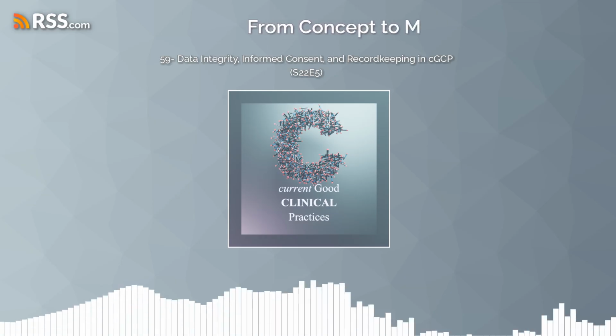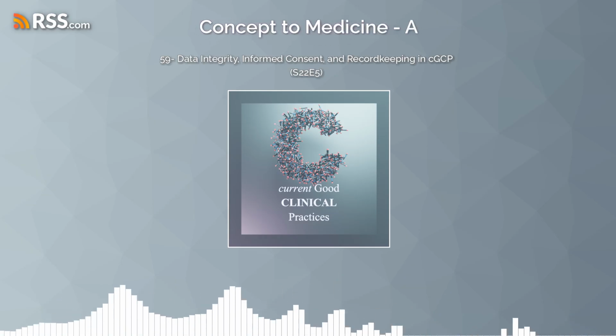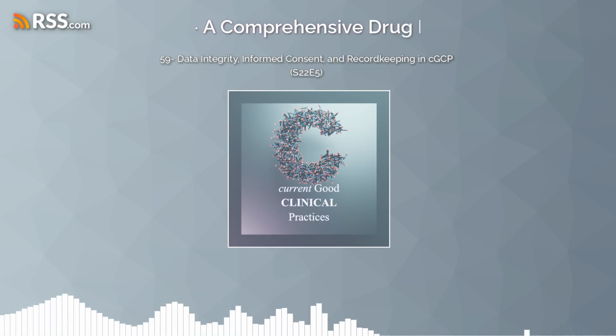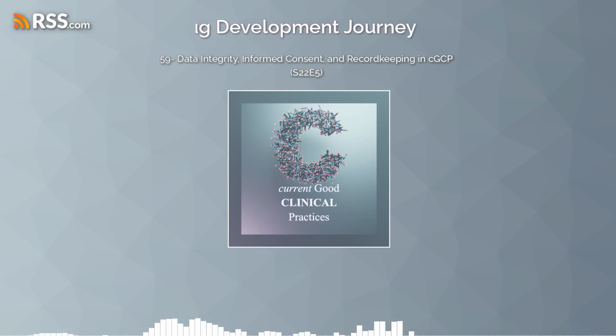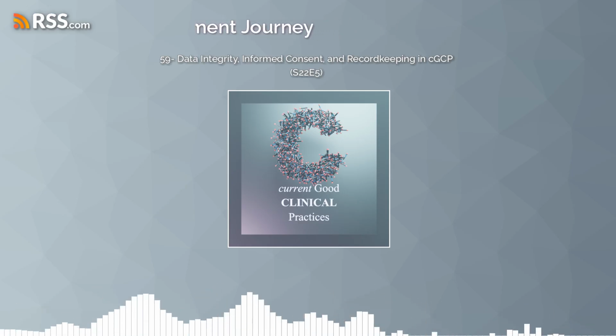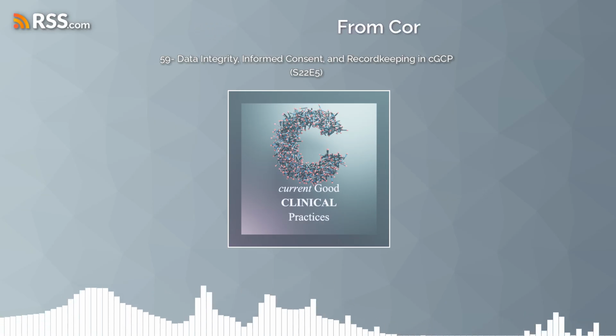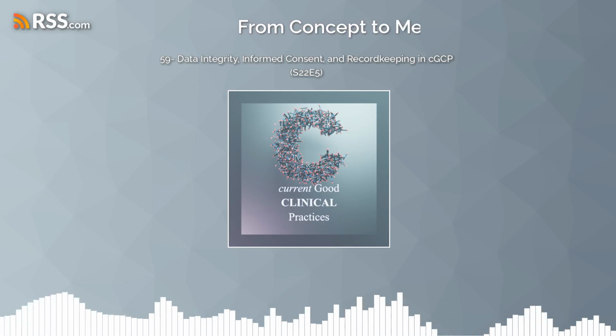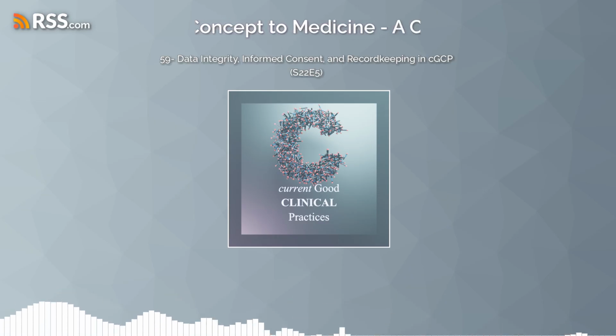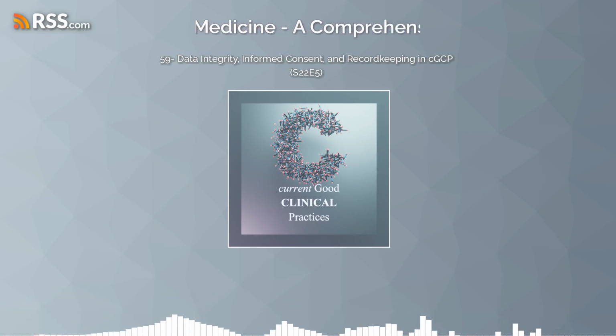And then there's operational qualification, OQ. This demonstrates that the equipment runs as intended across all the operating ranges it's expected to encounter. So making sure it actually does what it's supposed to do. Right. And then finally, you have performance qualification, PQ, which proves that the equipment consistently produces the desired quality product under normal production conditions. It's a step-by-step process to make sure the equipment is suitable and working reliably.